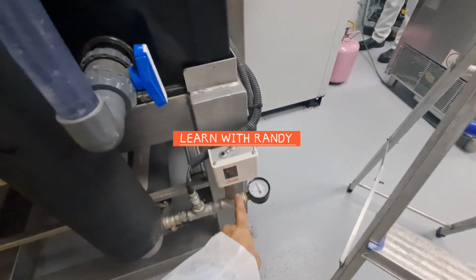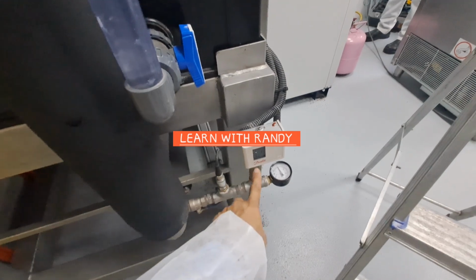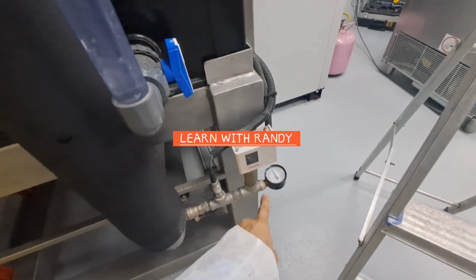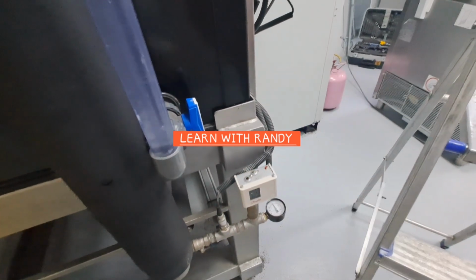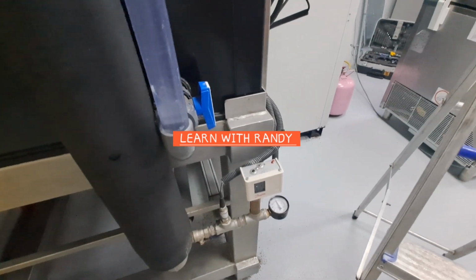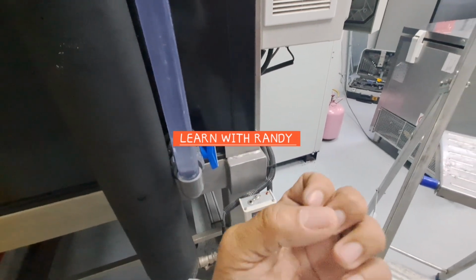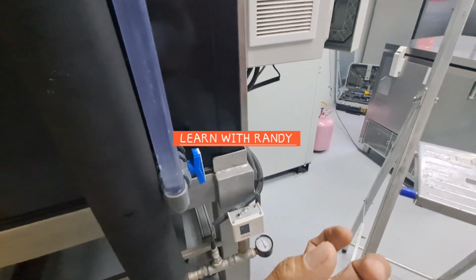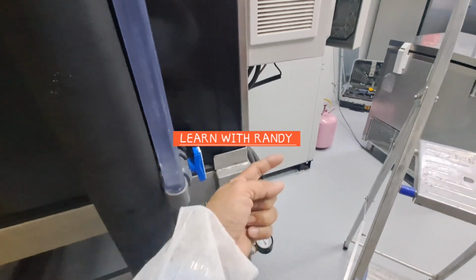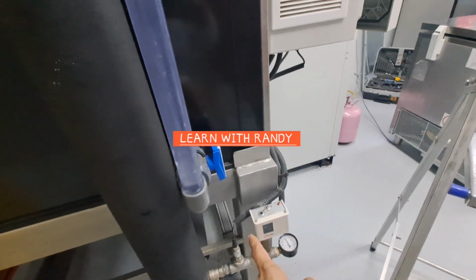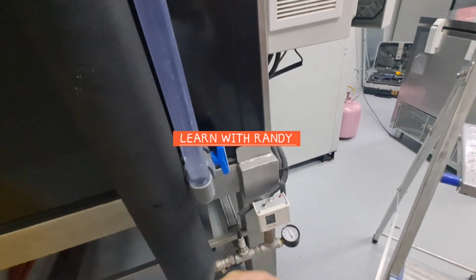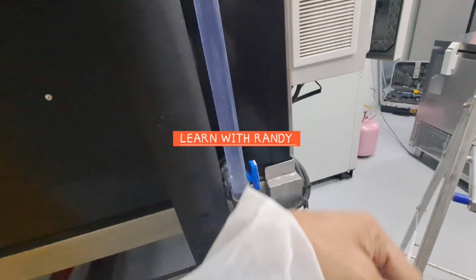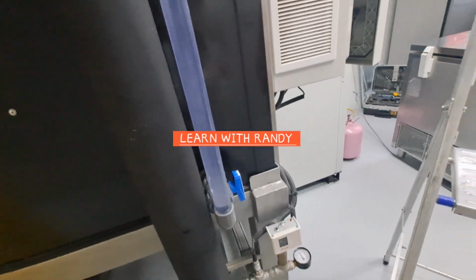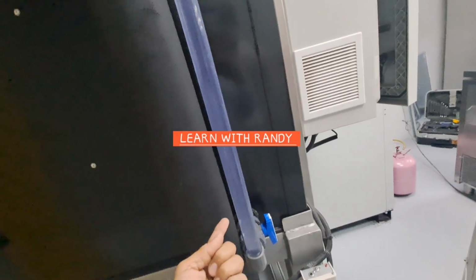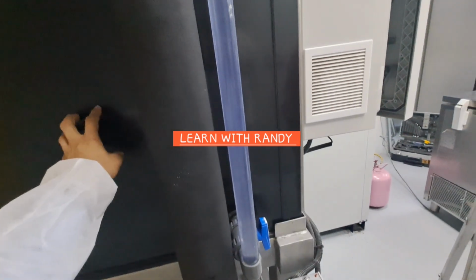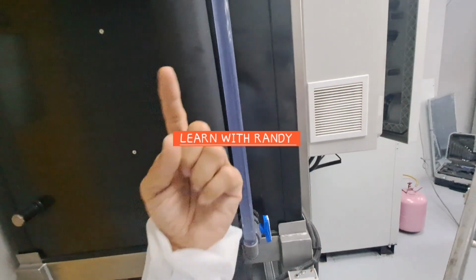So pump regulation pressure. You have the pressure switch here and the mechanical pressure switch. Both of them are connected to the controller. If there is no flow of water, then the heat exchanger will become icy. It will become overcooled, so this is the protection. The system is monitoring the pressure of the flow of the pump, and seeing whether the chilled water is flowing to the discharge tank or the aging tank and returning back to the chilled water tank. So it's only a matter of circulation.